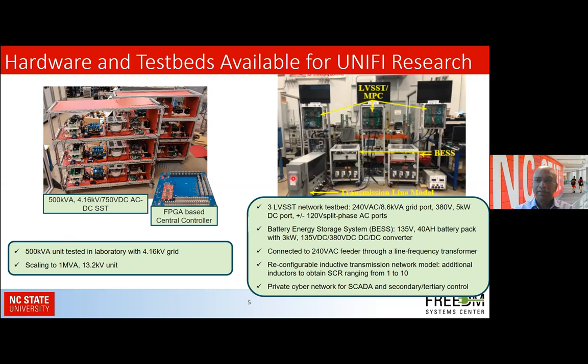And on the right-hand side, you can see some of our power electronics for a network system. So here we have 3 low voltage SSTs, single phase systems, connected to the 240 single phase grid. Here we have the battery storage units, and this is reconfigurable to include the transmission line network model here, which can be reconfigured to provide various short circuit ratios with which we can test controllers. And then it also has a private cyber network for SCADA and secondary and tertiary control.